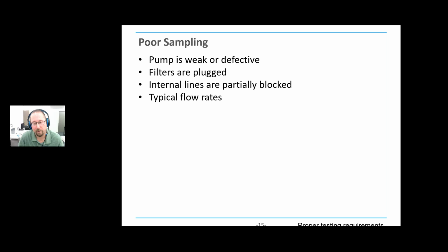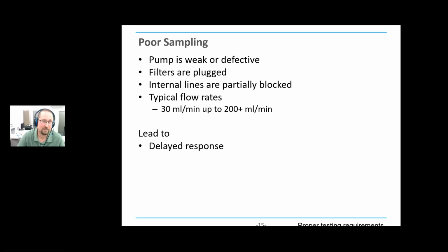Typical flow rates for any of these gas monitors range anywhere from 30 milliliters a minute all the way up to over 200 for anesthesia equipment. There are some as high as 250. All the newest ones are what they call low flow. It used to be that 50 was kind of low, and now you're getting down to 30. And I think there are even some now that are targeting 20. So if you have poor sampling, you can really get a delay in the response. It's just lagging way behind because you're not getting the sample through this long tube fast enough, or you can get incorrect readings because you're not getting enough sample in a fast enough time.